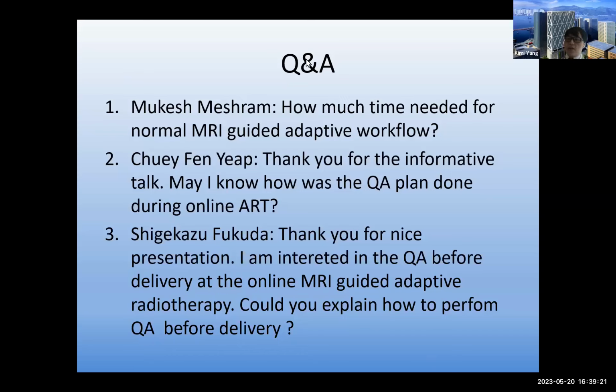We feed the software with the PDD and the beam profiles. Actually, such an algorithm cannot take the magnetic field into account. So we have to admit that it is not ideal to use a point dose calculation solution as the online QA system. More ideally, in the future, we will develop a 3D dose calculation for the online QA, and we also wish this 3D dose calculation will take the magnetic field into account. Yes.